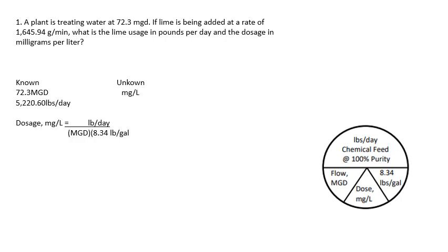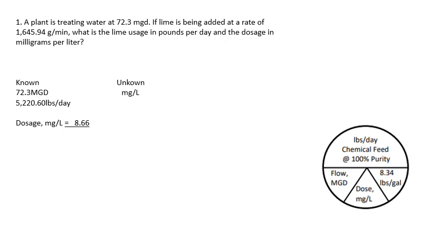Now that goes on our known column, and we can solve for dosage because we know the pounds per day. We have the million gallons and we're solving for dosage: 5,220.6 pounds per day divided by 72.3 MGD times 8.34 pounds per gallon. Make sure you do the math on the bottom first — it's top divided by bottom — otherwise you get the wrong answer. Your answer is 8.66 milligrams per liter.